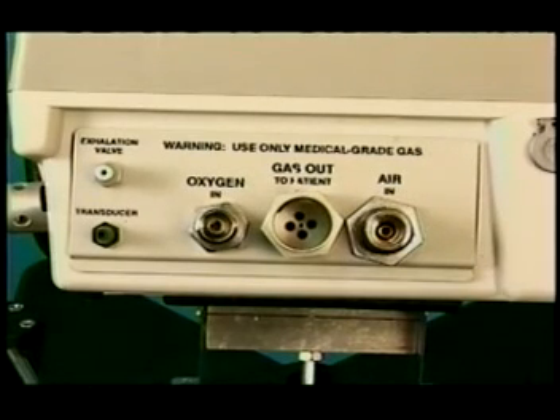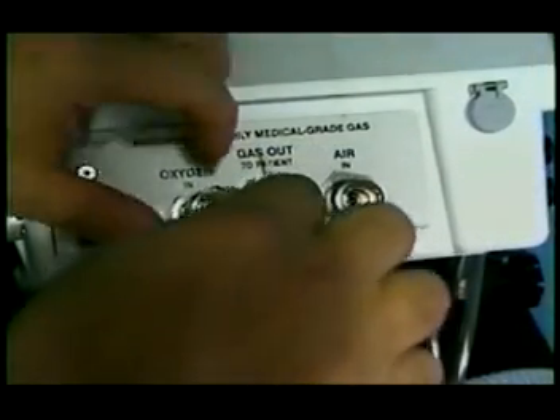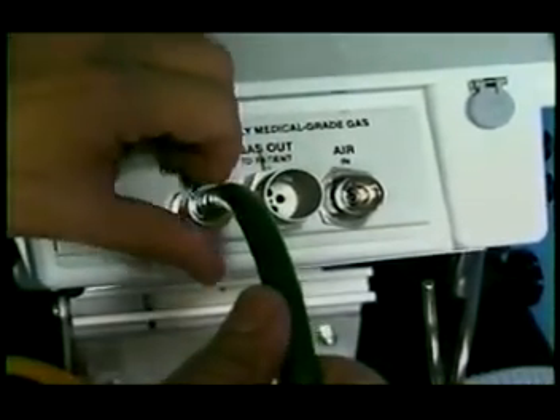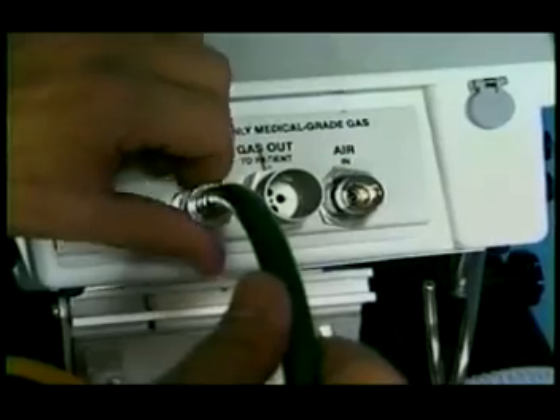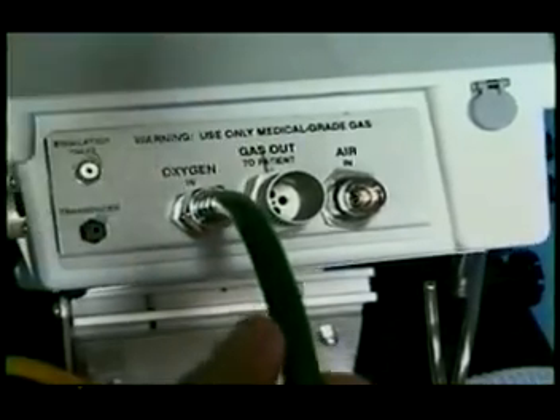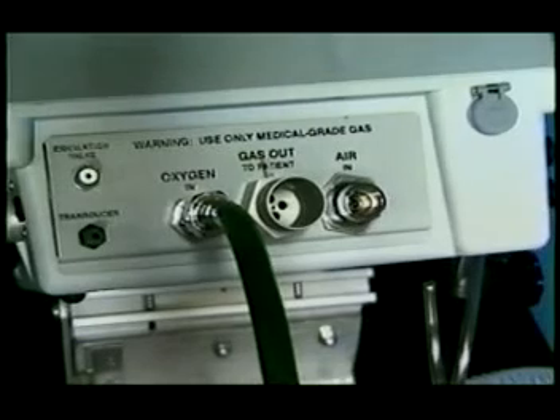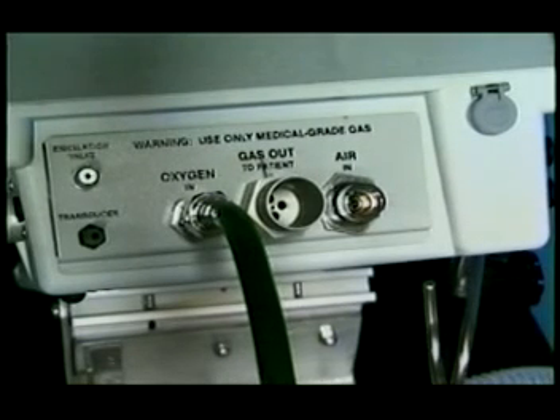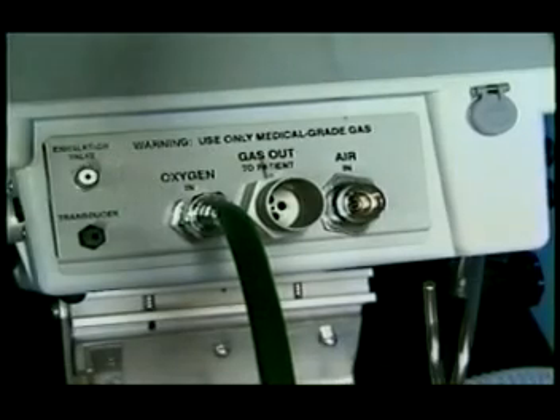Each fitting is sized in accordance with diameter index safety system dimensions, which are keyed and threaded for connection to a particular gas type. Color-coded hoses are provided with the ventilator. They attach to these fittings. Connect the oxygen hose provided, color-coded green, directly to the oxygen in fitting and its other end to a 50 psi oxygen source. This demonstration of operation does not use external air. However, if we were, the yellow-colored hose provided would connect from the air in fitting to a 50 psi air source.